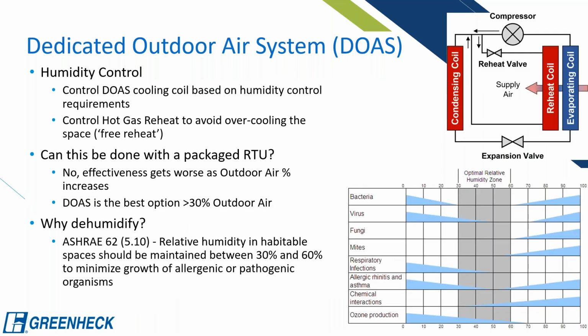So with a dedicated outside air system, the humidity control is done by the cooling coil, and then the hot gas reheat will actually, you can avoid overcooling the space with the free reheat from the DX system. And there's a little diagram up there to the right where it shows that there's essentially a second condensing coil inside the airstream that will reheat the dehumidified air so you don't overcool the space.